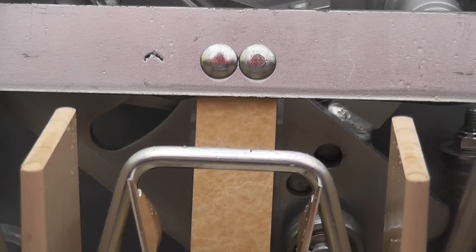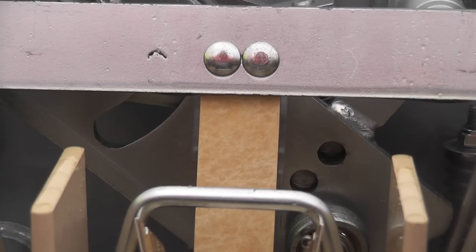These things — it's important that they're in the contacts properly and there are no signs of arcing. Those are the probes. Let's see if we can get the camera on there to make contact. These things are sliding into these female contacts. It's very important that the thing makes properly. Check that — good positive contact. It's really important.